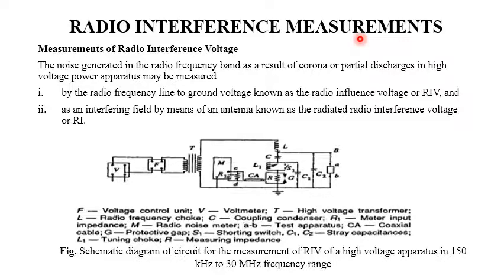So it is important to see that the noise voltage generated in the radio and other transmission bands is limited to acceptable levels, and hence radio interference voltage measurement plays an important role. It has been found that the surface conditions of the overhead conductors subjected to high voltage stress, and varying atmospheric conditions, will influence the magnitude of the noise voltage which is produced. In the case of solid insulators, the bonding between porcelain and the metal pin, the binding of the high voltage conductor and the insulator surface, and the surface pollutions were found to be the source of the noise.